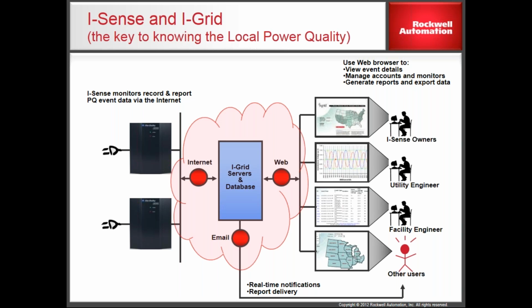The other thing, because it's in this cloud environment, there's no limit to the number of people who can get that report—not only the instant report, but also go back and pull out a whole year's worth of data. And there's no limit to the number of users, and every user can have their own adjustment. The plant manager probably doesn't want to know about every transient that hits the plant, because there are a lot of them and they don't really affect you much. But when the voltage drops below 60%, you probably went down—maybe that's the time to send him a message.